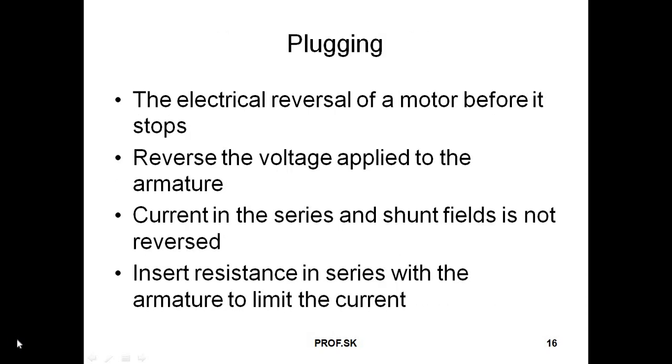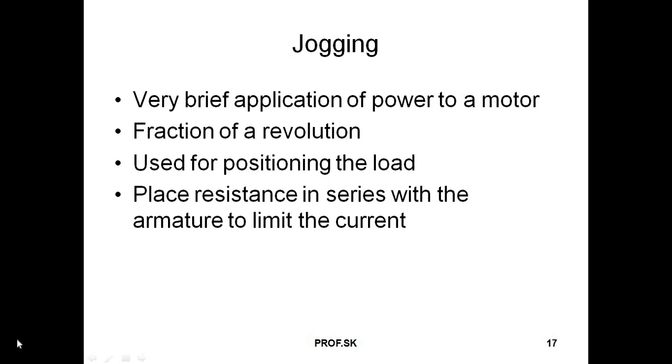Plugging. The electrical reversal of a motor before it stops. Reverse voltage is applied to the armature. Current in the series and shunt field is not reversed. Insert resistance in series with the armature to limit current. Jogging. Very brief application of power to a motor, a fraction of a revolution, used for positioning the load. Place resistance in series with the armature to limit the current.